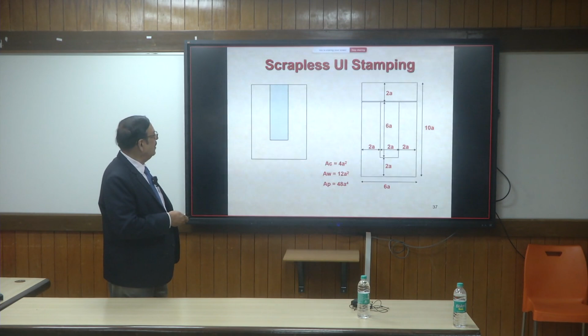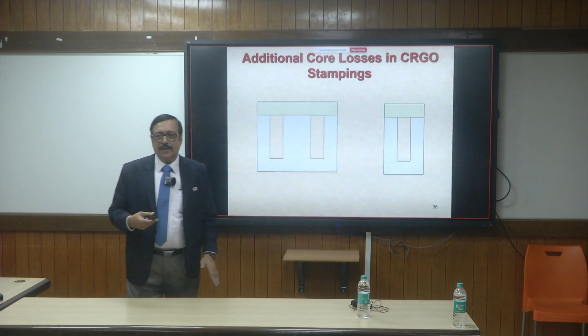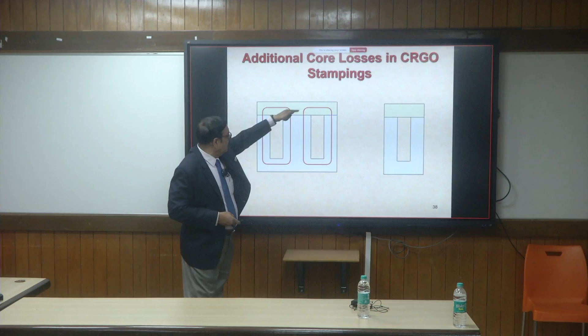Okay. We may make a small transformer out of CRGO stampings, but the orientations will be something that you can see here because of the lines. The flux has come from this part. Now, if I make this out of CRGO, we think the core losses will be less compared to CRNO. It may not be so, because you have the flux path and you have additional losses at this point where the flux is entering perpendicular to the direction of orientation. So you will have additional losses at these points. So ultimately you will find that the difference in efficiency is negligible.